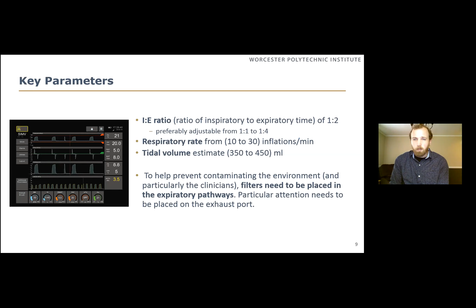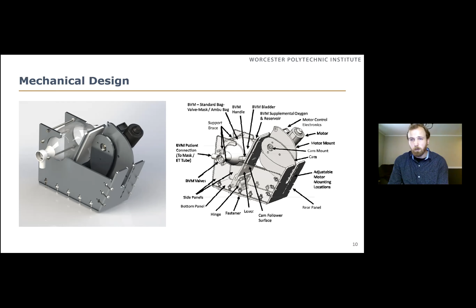So we came up with this mechanical design, which is very basic. It mounts the motor with this cam on it. So the cam sets the I to E ratio, and that cam pushes against a lever, which crushes the bag. So it's a very simple mechanism. There's no special electronics or controllers. It's just a windshield wiper motor and a simple industrial timer that can be basically any industrial timer that you need to adjust the respiration rate.